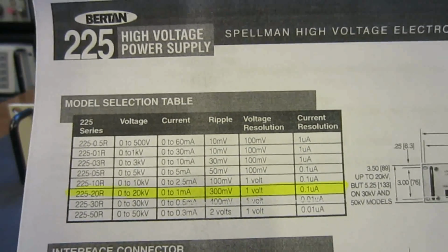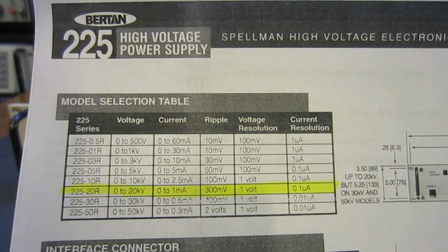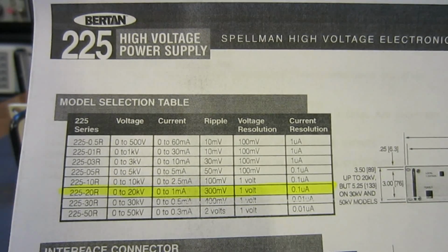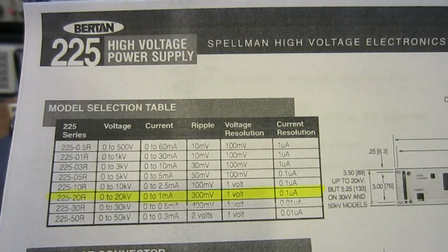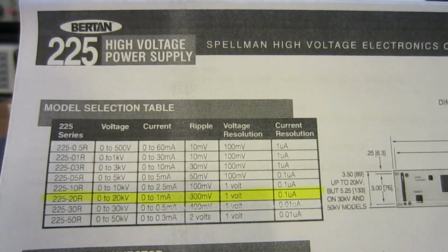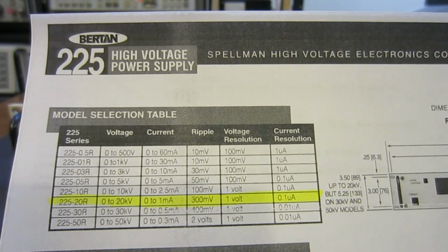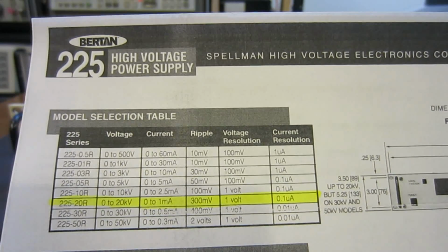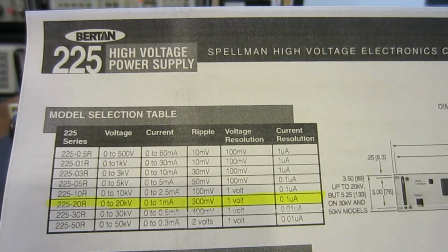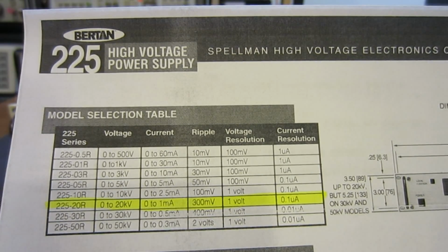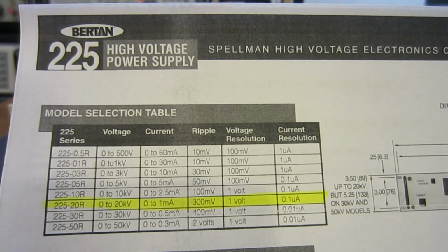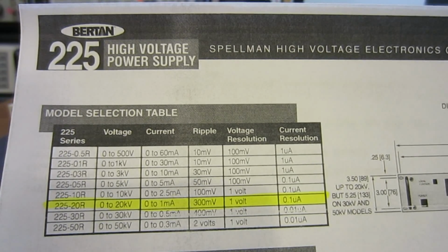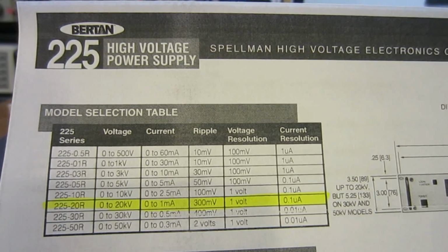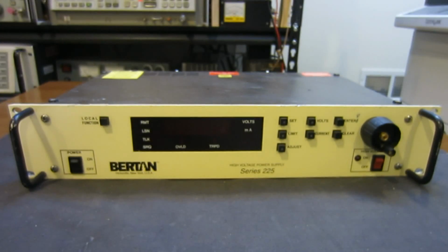And we can take a look at other aspects of this unit. If you take a look at the line I highlighted here, you will see that the current resolution for this 0 to 1 milliamp output is 0.1 microamp, and the voltage resolution is 1 volt. So what does this tell you? I'm thinking that it has at least a 15-bit DAC inside, because to have more than 20,000 intervals, you will need at least a 15-bit DAC. So we will see later what kind of a DAC or an ADC it uses inside. Anyway, so that's the specifications, and now let's take a look at the unit itself.